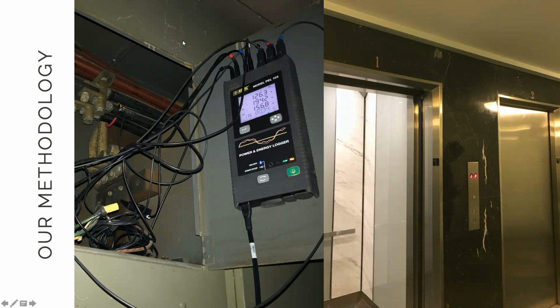Had we instead relied on just the submetering bills and Con Ed data, we might have significantly underestimated the size of those critical loads. Speaking of those loads, the data logger did help us make sure that all of those critical loads at the building are in fact behind the PLP meter, meaning electrically this would be a relatively simple operation and that we could just power the entire PLP meter during a blackout.